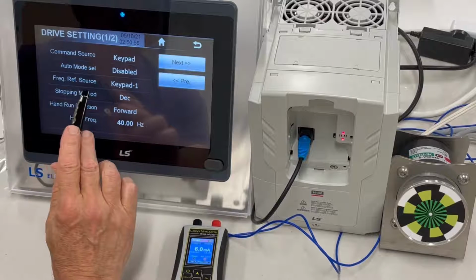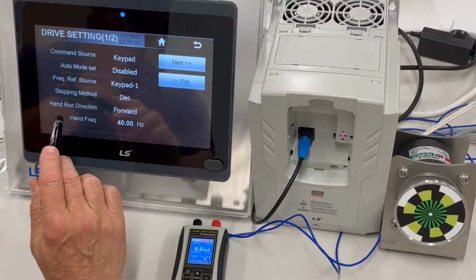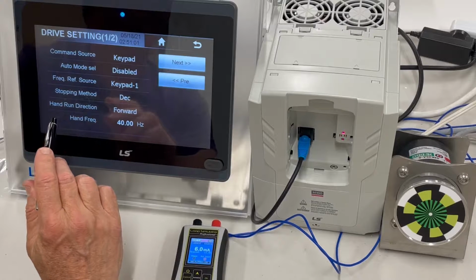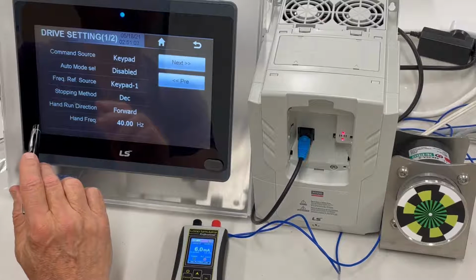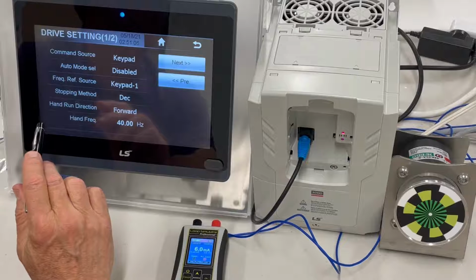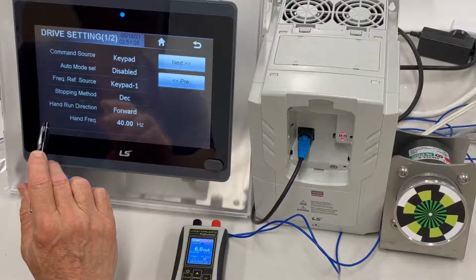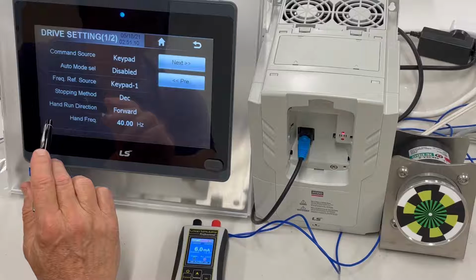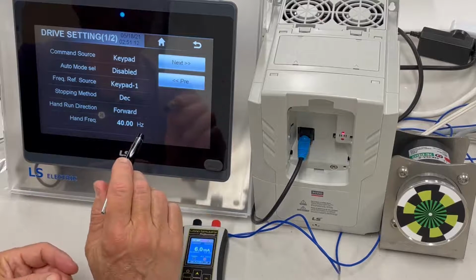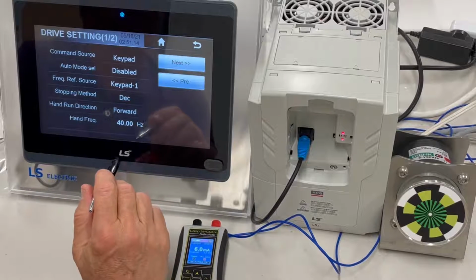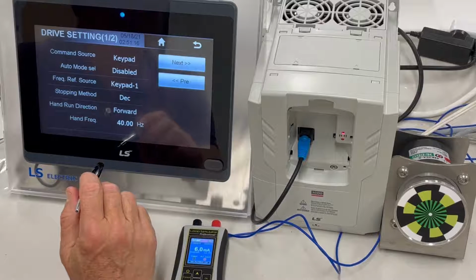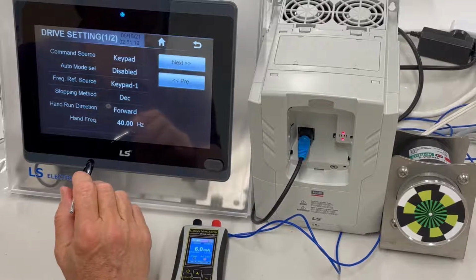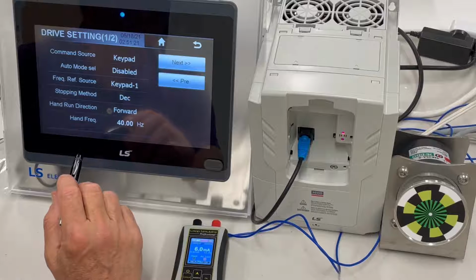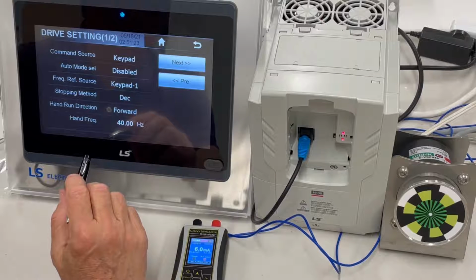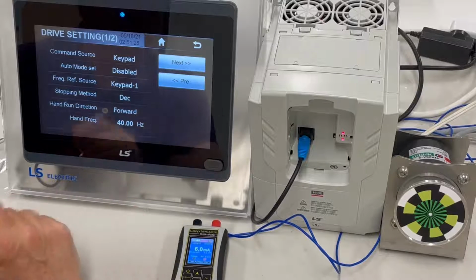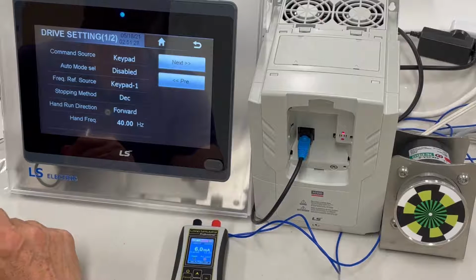The auto mode select is disabled, and what that means is that if we were to have an error, a fault, or go to sleep, the drive comes from the factory preconditioned to need a signal or a connection, like either a keypad or external signal, to restart it. In this case, we don't want to do that. If it goes into sleep mode, we want it to come out of sleep mode without having another signal go to it from a keypad or an external device. We want it to be self-contained within the logic of the drive.